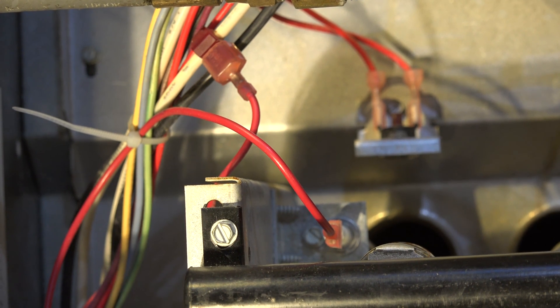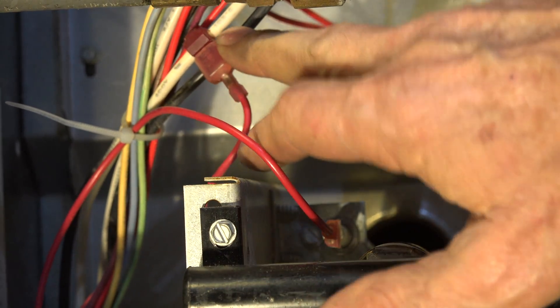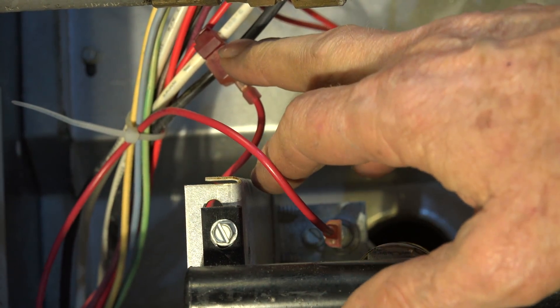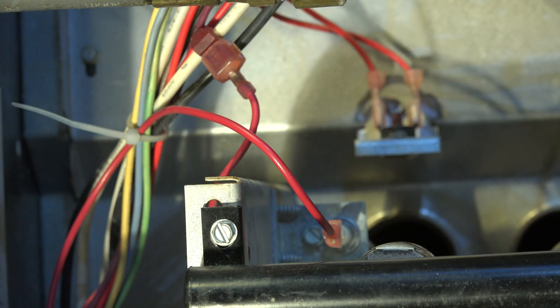It's not hooked to the chassis ground. It is a neutral but the neutral and chassis ground are separated on these furnaces. What the heck? How would this make a difference? It actually has a little metal spike in it that goes through and touches the neutral wire.